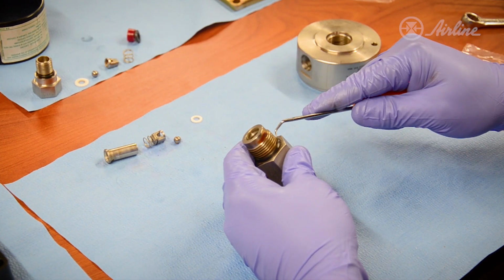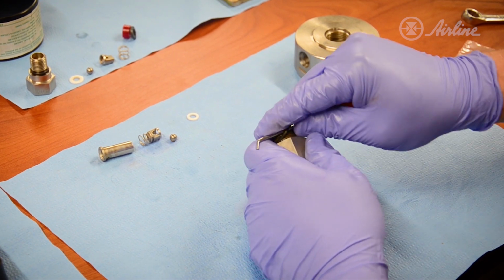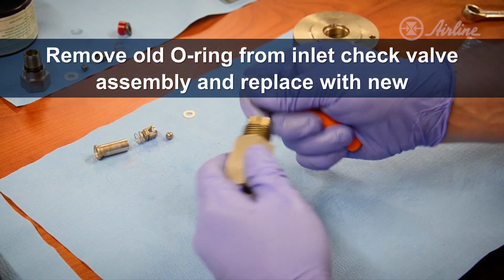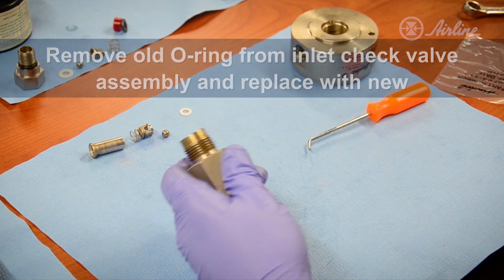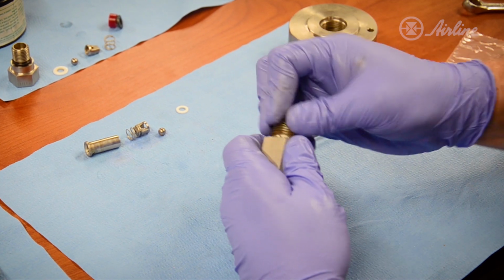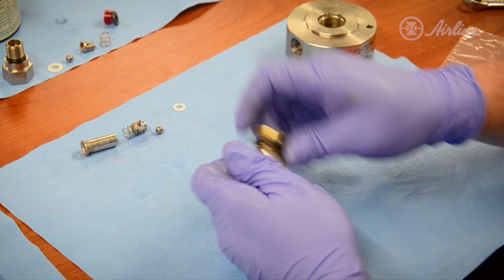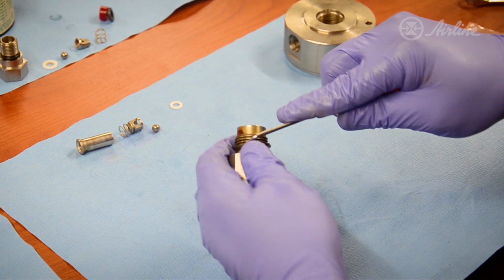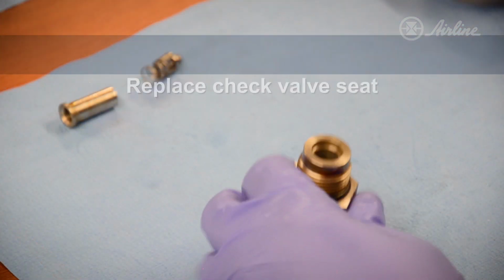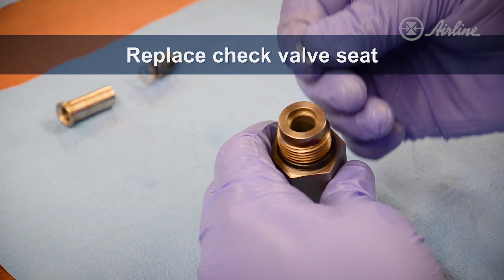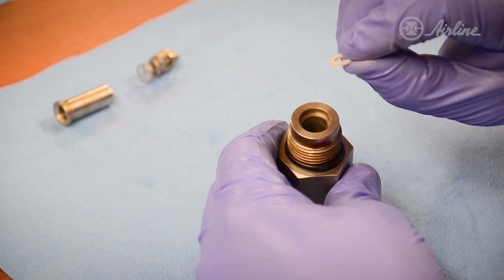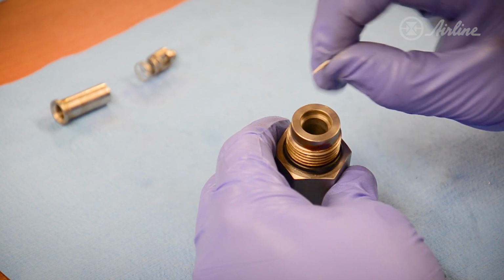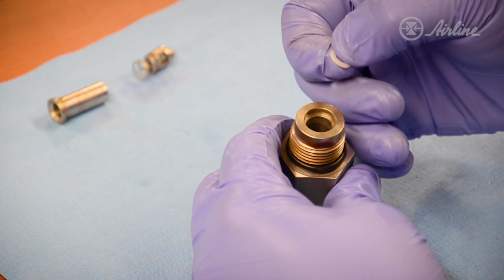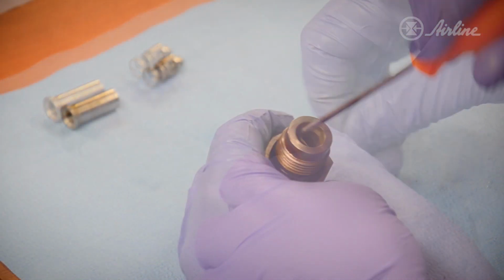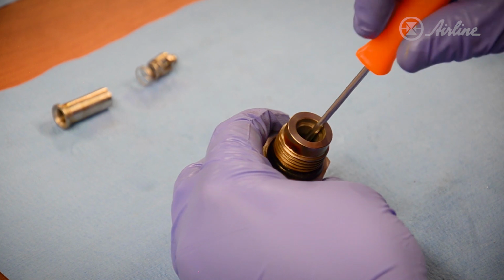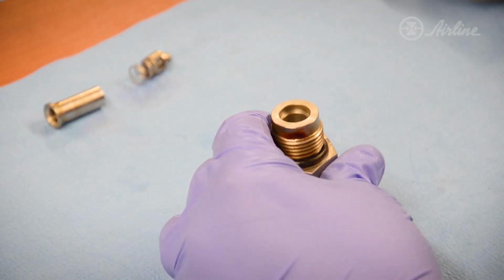Next part of the fluid section repair is to reassemble the inlet check valve assembly. We'll start by removing the old O-ring that seals this to the pump body and replacing it with a new O-ring that came in the seal kit. Make sure you lubricate the check valve assembly O-rings before installation. So first thing we'll do is replace the check valve seat from the inlet check valve. The inlet and outlet check valve seats are slightly different sizes. Use the assembly drawing and bill of material to ensure you're installing the proper seat on the proper check valve. And then we can gently use one of our picks to make sure that that check valve seat is just pushed to the bottom of this fitting.